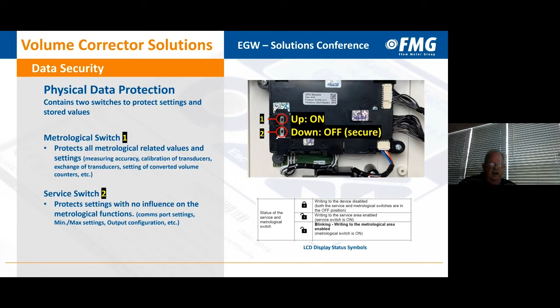Software data protection. So within the software that's used on the volume corrector, at least this one, there are 5 levels of security. So you can leave it completely open and anything and everything can be changed. Or you can lock it down. The guy in the control room doesn't need to go in and make changes. He just needs to read it. So you can give that kind of access. The field people, you can give access on several levels. Not everybody needs to go in and change the settings within the corrector. Most of the time, they either need to read it or they need to maybe change out a transducer. Those can be done. Those security levels can be set. So again, 5 different levels available.